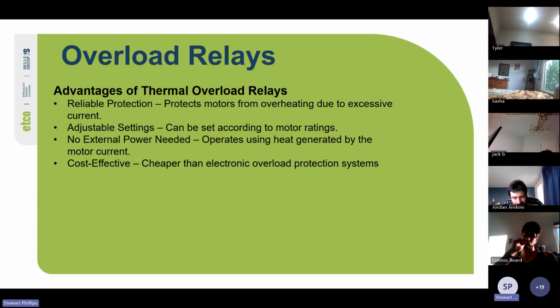You've got adjustable settings that can be set according to motor ratings. So depending on the size of the motor, you can change the amount of current that it will trip at. This is good because you can buy a whole bunch of overloads and then adjust them per motor, if you've got different motors set up in your work area. It needs no external power, so it operates using heat generated by the motor current, so you don't need to run a control circuit for it. It does it itself. Cost effective, it's cheaper than electronic overload protection systems.